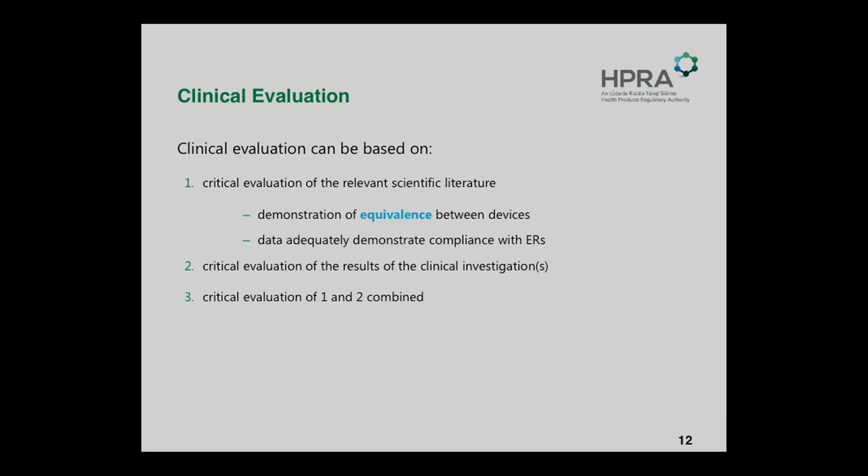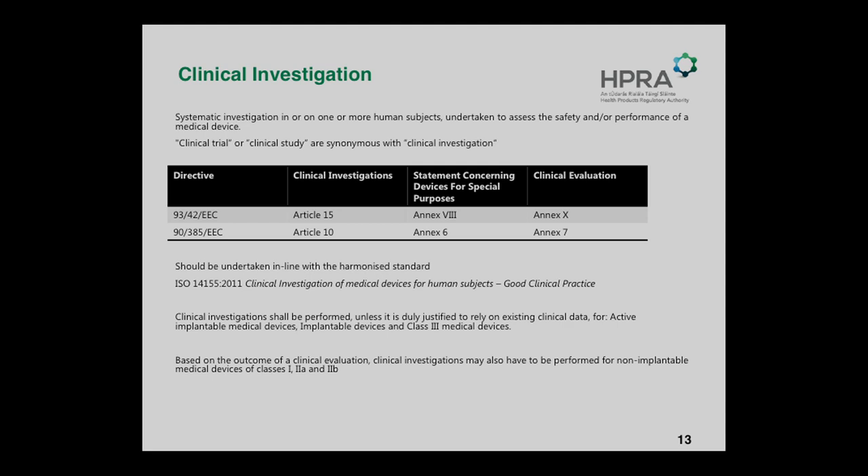Where would you involve us in a clinical investigation? There are a number of scenarios: where it's a completely new device, where you're using new materials, a new intended use for an existing device, or where it's in a different location. In all of those areas, clinical investigation may be considered. Where we wouldn't generally be involved is where it's early clinical or academic research with no regulatory purpose and no intent of bringing the product to market or achieving a CE mark. We also wouldn't be involved where it's an existing CE-marked device being used within its intended purpose, where the manufacturer or investigator is seeking further information.